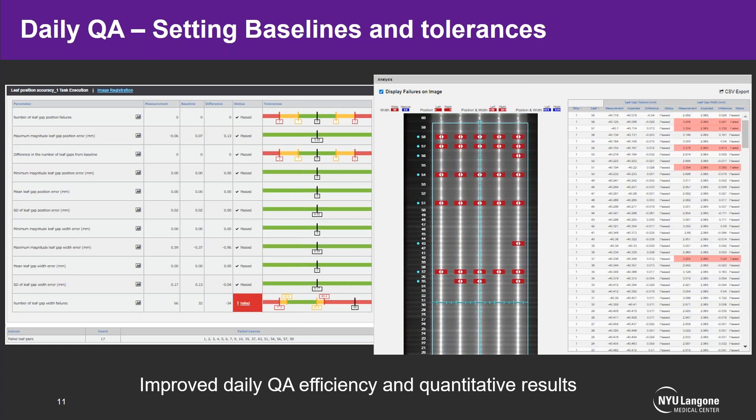Things we were just qualitatively looking at, like MLC QA, now have rigorous numbers where we can check each specific leaf pair if needed. The therapists have been very pro-SNC Routine to the point that they're rearranging some tests to improve their own efficiency and get through morning QA even faster.